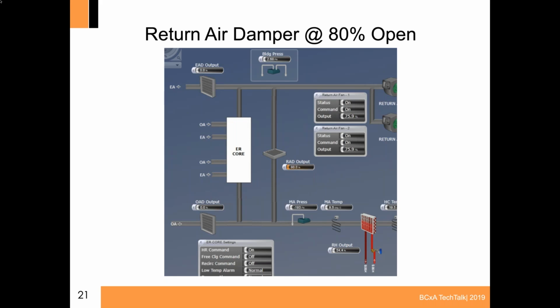Prior to us going in and getting pictures and snapshots for this tech talk, we'd already spent a lot of time on other schools finding out what that damper position should be. So that was our starting point, and then we worked down from there. So you can see that the mixed air temperature off the core has now jumped up to 9.5 degrees from 6.5 degrees Celsius or 43.7 degrees Fahrenheit. So we're seeing some positive impact.